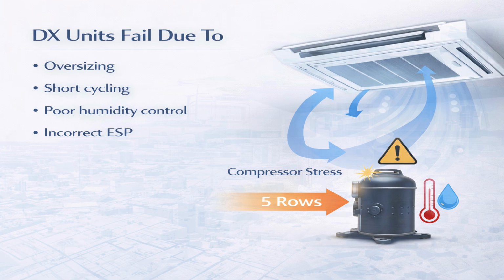This is why DX systems require particularly careful selection. Accurate load analysis is essential. The unit's sensible heat ratio must align with the space requirements, and fan static pressure assumptions must reflect real duct and filter conditions. When any of these are overlooked, DX systems may still be approved and installed, but they will rarely deliver stable, efficient long-term performance.